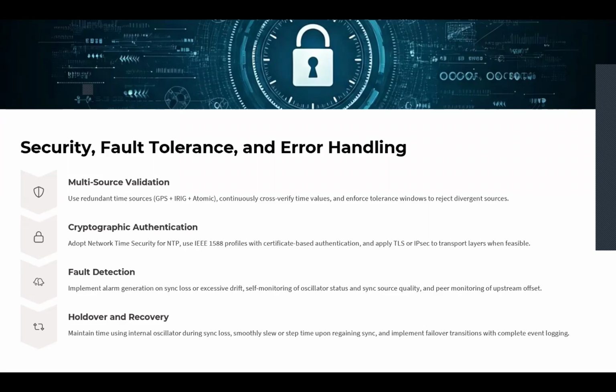The most powerful method for resilience is multi-source validation. Instead of relying on a single GPS or a master clock, the fault-tolerant system accepts input from multiple independent time sources and cross-verifies them. If one source drifts beyond an allowed tolerance window, it's rejected or demoted. This standard IEEE 1344 also recommends architectures where a secondary clock is always standing by. If the primary master fails, the secondary one kicks in automatically.